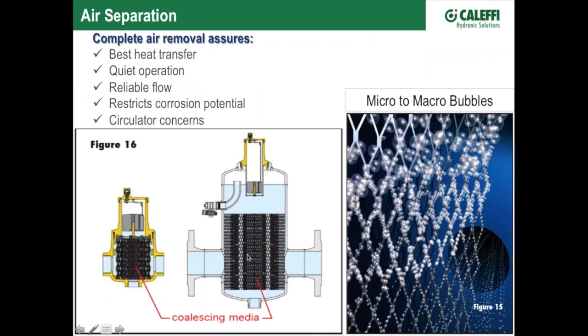So what we do is we put a media in there. We call it a coalescing media. I sometimes call it a collision media, because we're bringing the flow through that media, and it drives these little bubbles. These little bubbles will cling to the sharp surfaces on this media. The little bubbles rise up, join the bigger bubbles, and eventually they can come out the vent in the top. This is important because we want the best heat transfer. We've got to get these little bubbles that might be coating our heat exchanger out of the system.